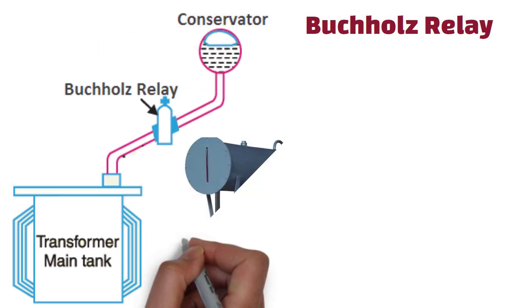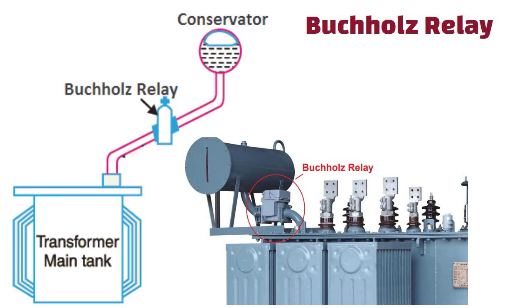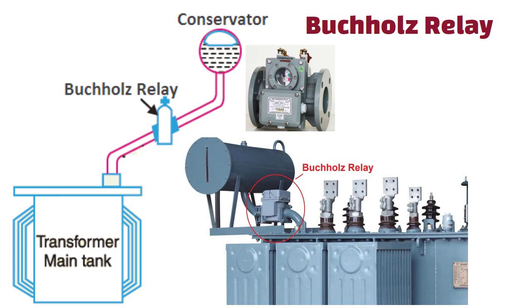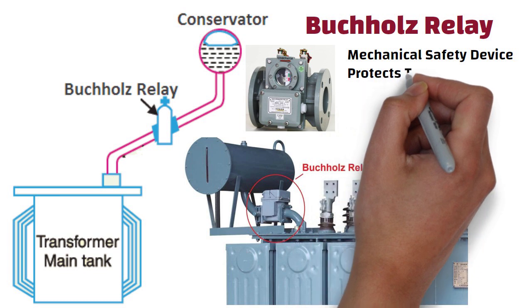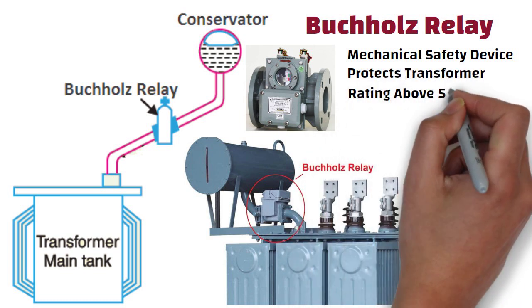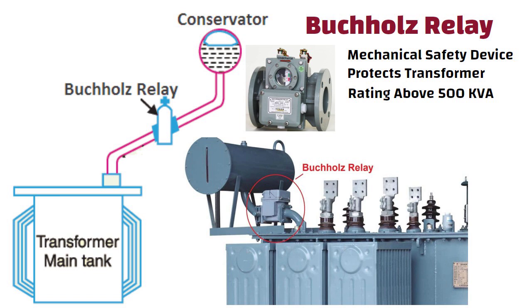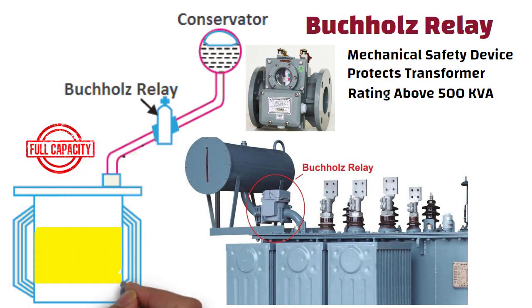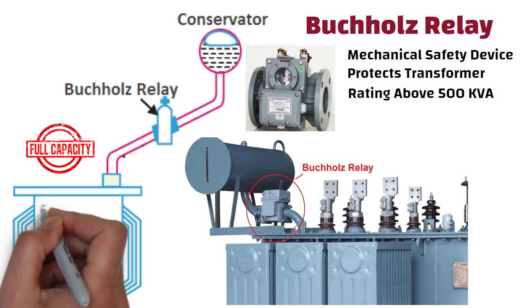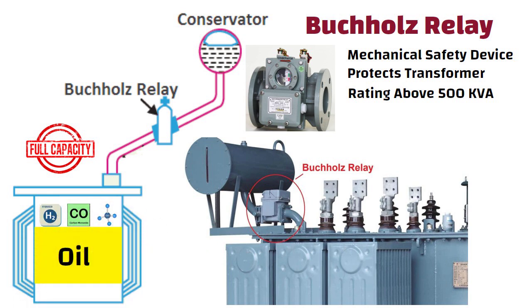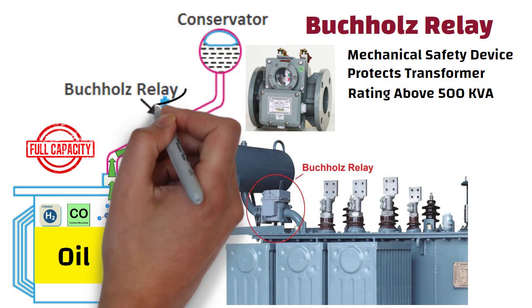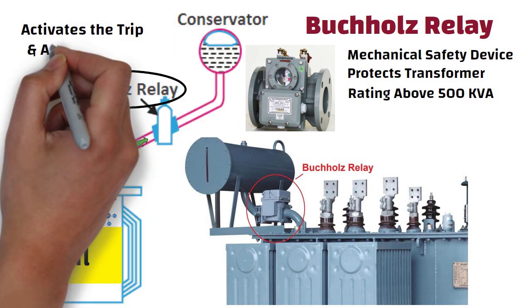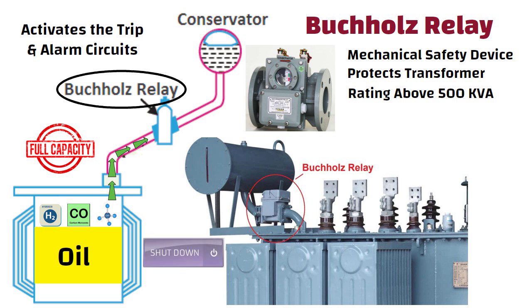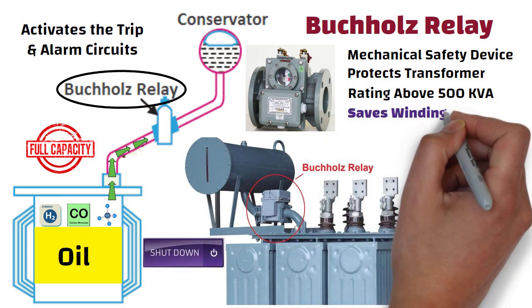Now let us understand the Buchholz relay. The Buchholz relay is located in between the main tank and the conservator tank. You can see the actual image of the Buchholz relay here. Basically, it is a mechanical safety device which protects the transformer. If the transformer rating is above 500 kVA, then the Buchholz relay is used. When the transformer runs at its full capacity, the oil generates enough heat to decompose into hydrogen, carbon monoxide, methane, etc. These gases gradually move towards the conservator tank through the connecting pipe. The Buchholz relay senses these gases and activates the trip and alarm circuits. In simple language, it shuts down the transformer. So ultimately it saves the winding and insulation from burning.